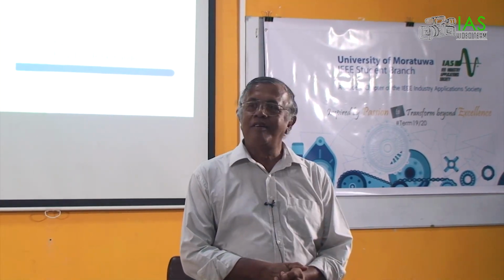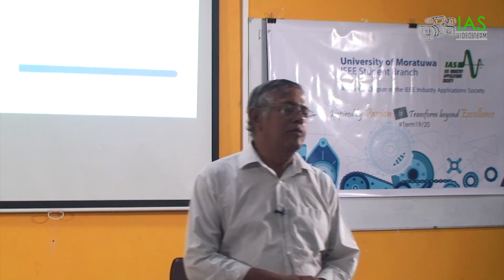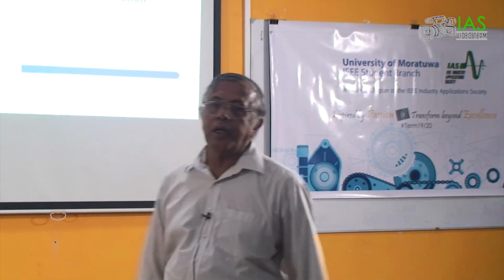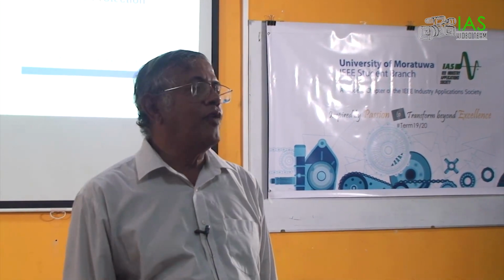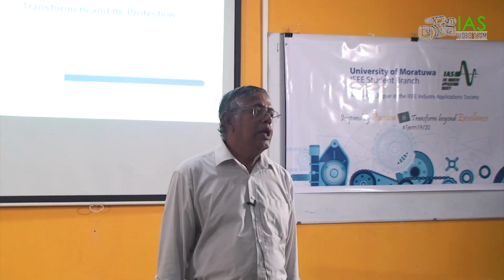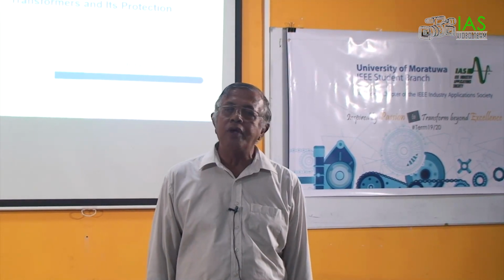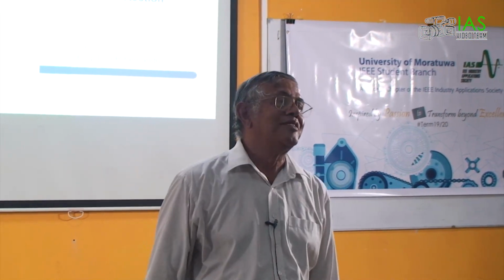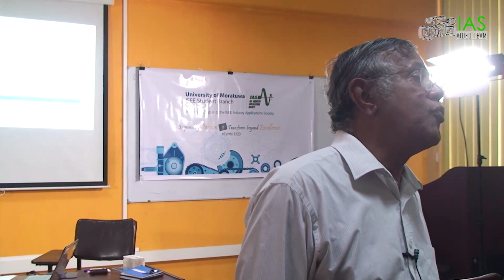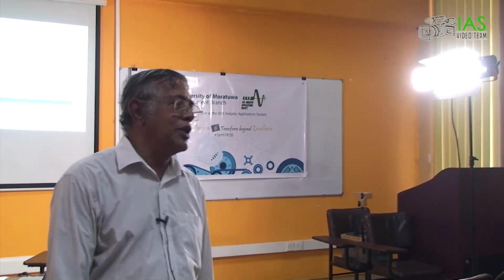I have one question for you all, because you have just come from the training. You have now seen a transformer and a distribution transformer. What is the percentage impedance of a transformer? Anybody? Percentage impedance of a 400 kVA distribution transformer? Yeah, about 4% or 5%.